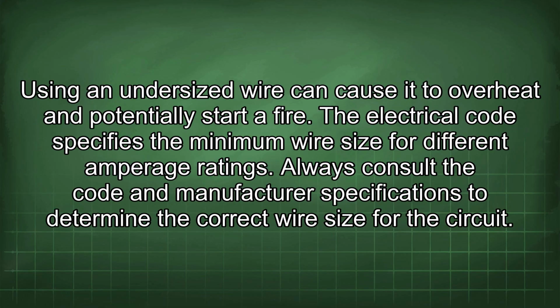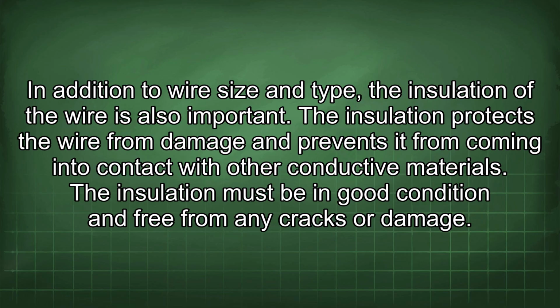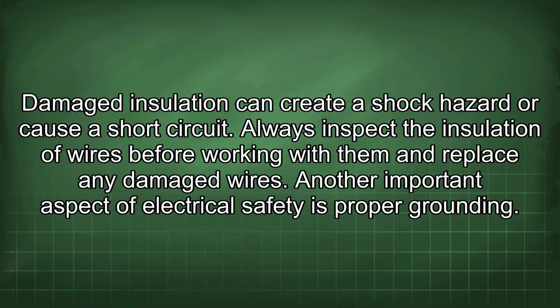Furthermore, the size of the wire, or its gauge, must be appropriate for the amount of current it will carry. Using an undersized wire can cause it to overheat and potentially start a fire. The electrical code specifies the minimum wire size for different amperage ratings. Always consult the code and manufacturer specifications to determine the correct wire size for the circuit. In addition to wire size and type, the insulation of the wire is also important. The insulation protects the wire from damage and prevents it from coming into contact with other conductive materials. The insulation must be in good condition and free from any cracks or damage. Damaged insulation can create a shock hazard or cause a short circuit. Always inspect the insulation of wires before working with them and replace any damaged wires.